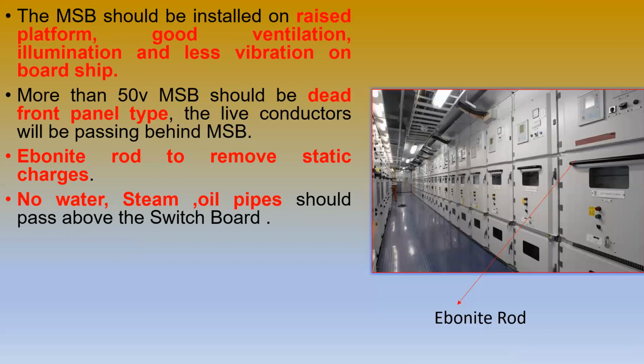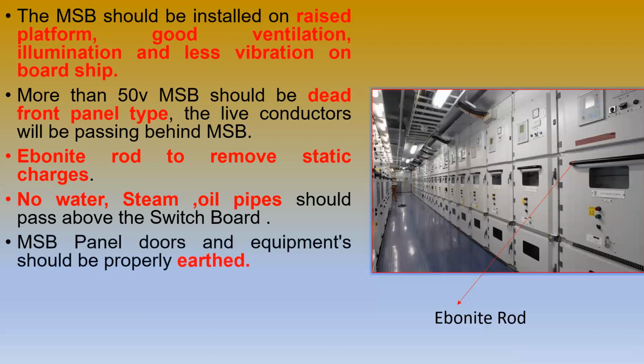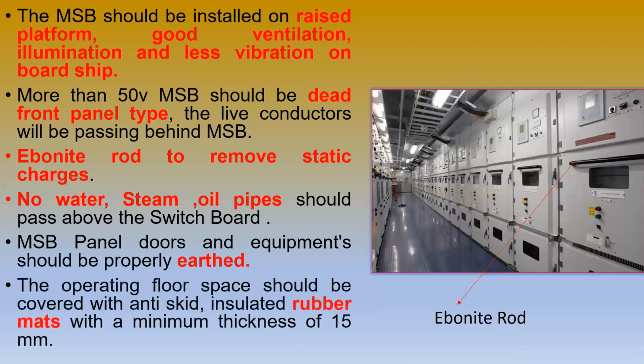So during the installation, we have to look at that. There must be panel doors and the equipment should be properly earthed. This will give extra safety to the devices. The panel boards are earthed. For the operating floor space, the space around the MSB, an insulated rubber mat of a minimum thickness of 15 mm should be placed. The rubber mat will be placed here, just 15 mm in thickness.